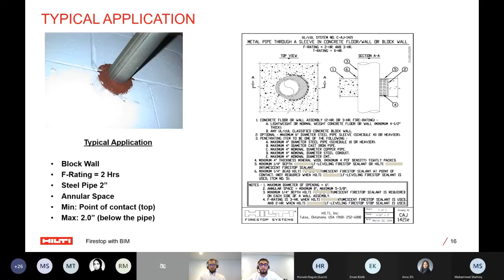Then we look at numbers 4 and 5, which represent the fire stopping solution for this specific case with this specific annular gap. So here it says that it consists of some rock wool and some fire rated sealant as well. Now, we said that if you have an as-built case that does not match any tested system available, then we refer to an engineering judgment.